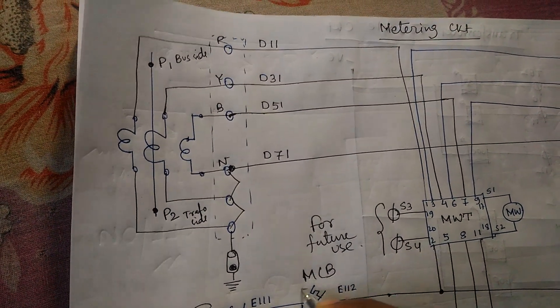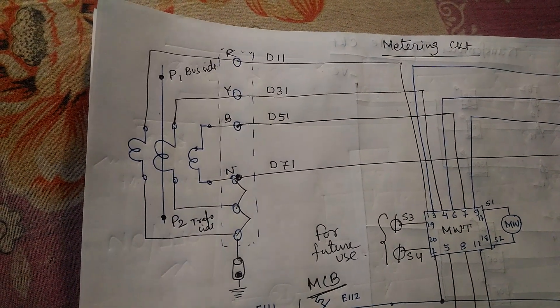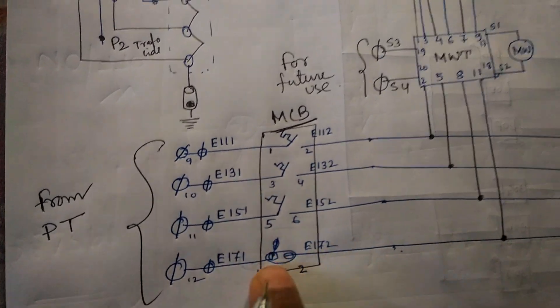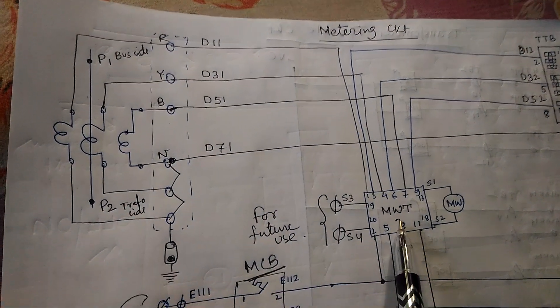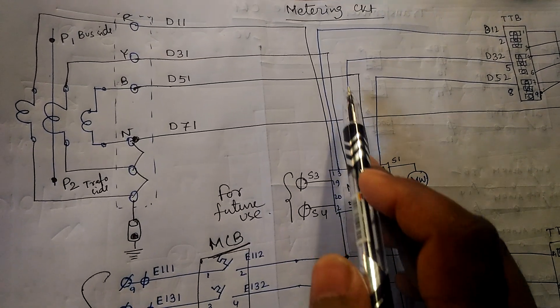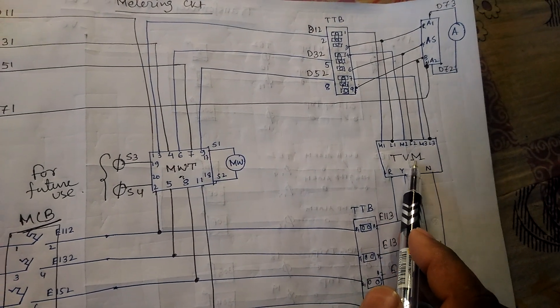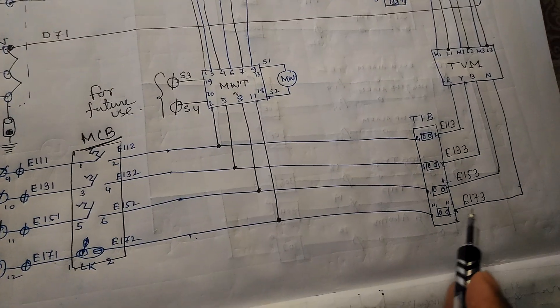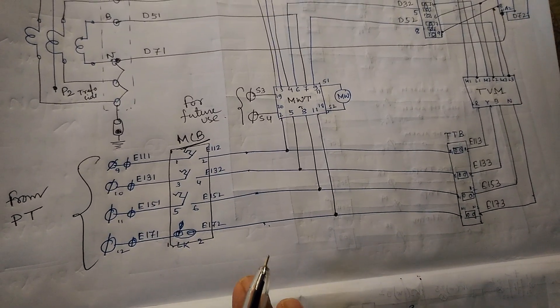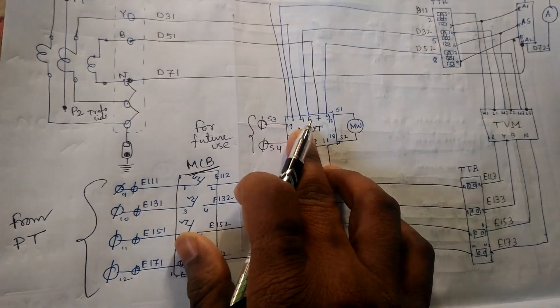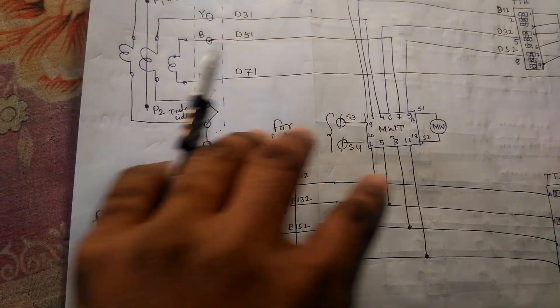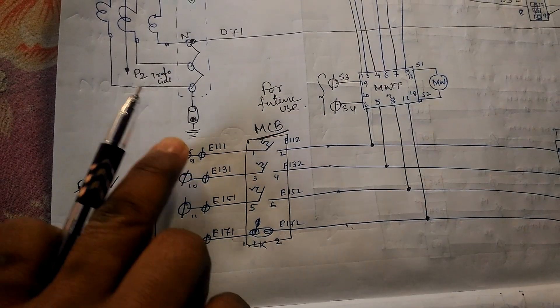The PT voltage comes through MCBs. We are connecting the CT terminal to the megawatt meter terminal, and also connecting to the TVM meter and to the ammeter selector switch, as per this diagram. The metering circuit connections come from the PT through the test terminal block.